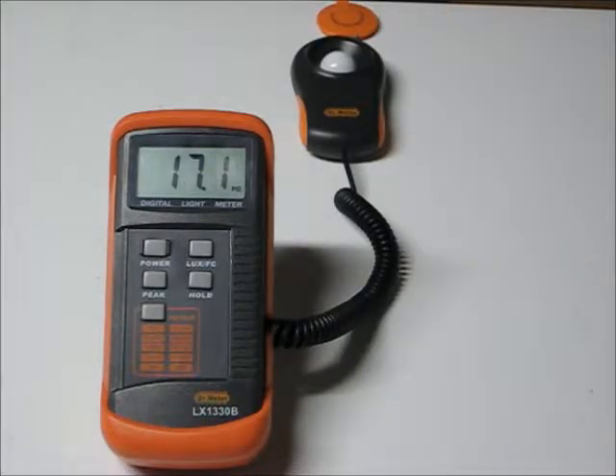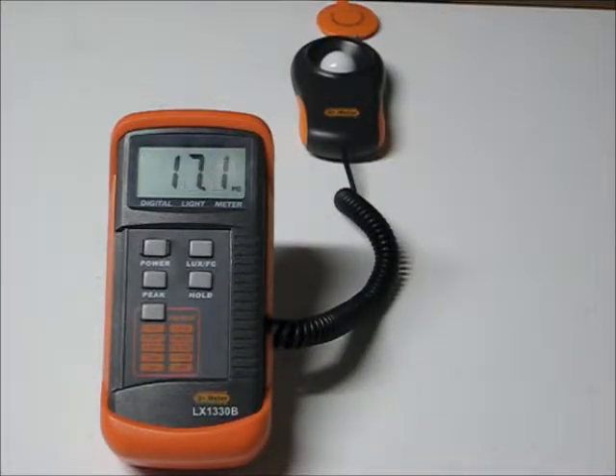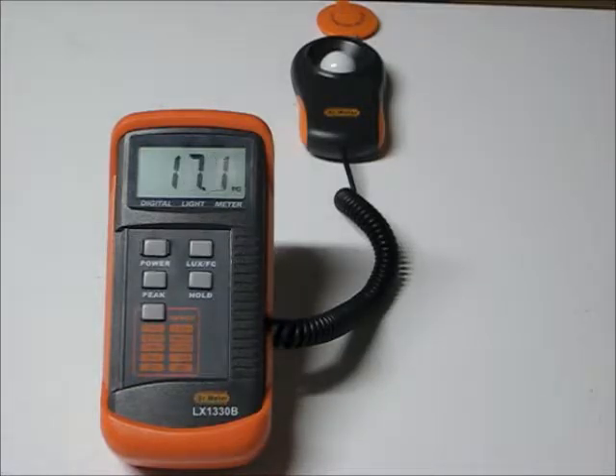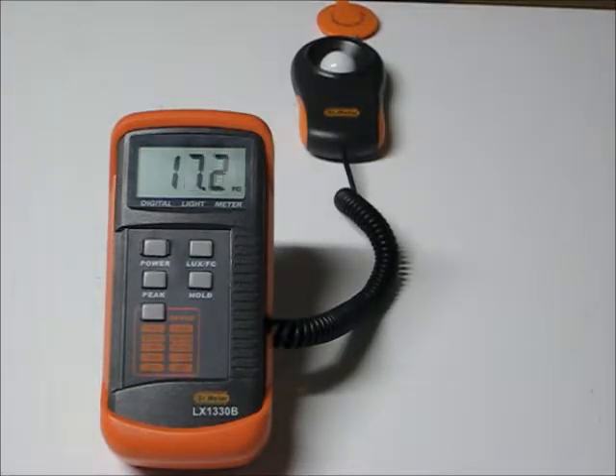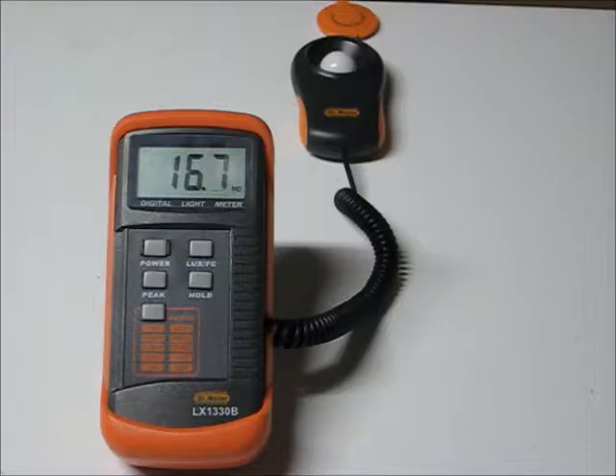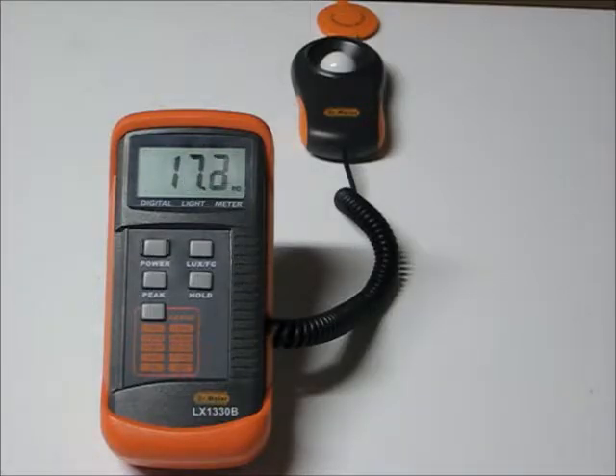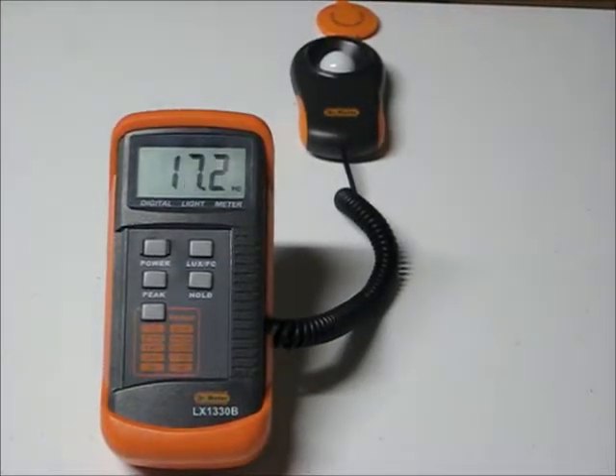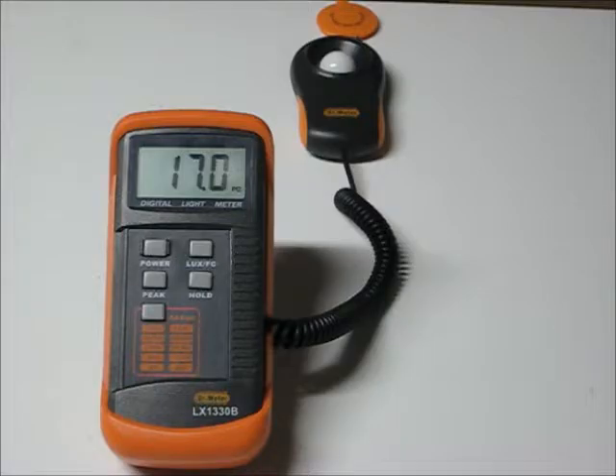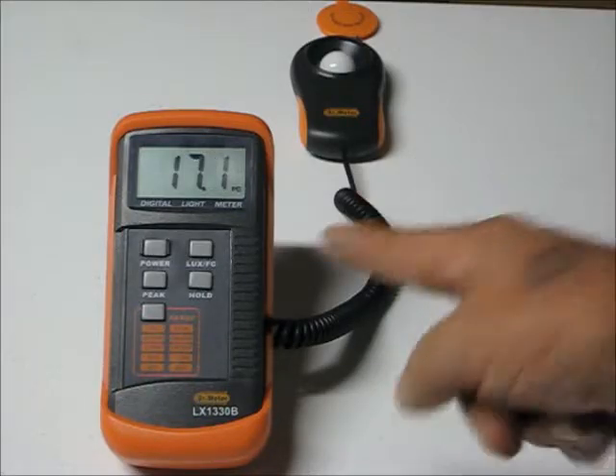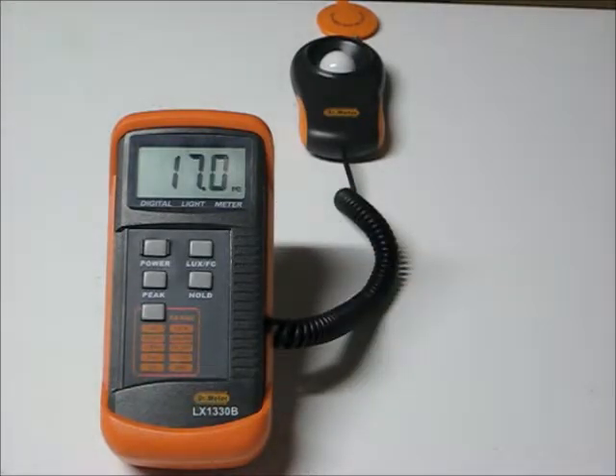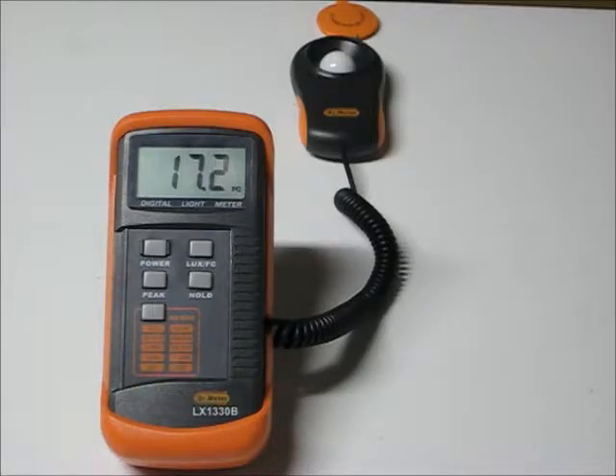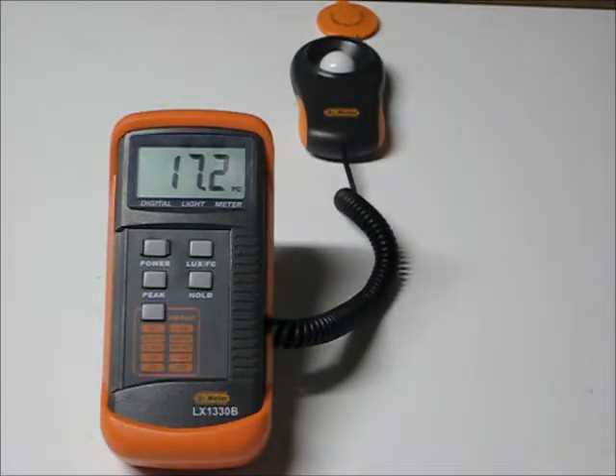Okay. Well, we're actually more like 16.5 to 17, fluctuating somewhat. Let's see what happens when we put the 25 watt bulbs back in. Okay. Somehow, after the total calibration, we came out about a foot candle high. We're reading 17 versus the 16 we were shooting for. That's not too bad.